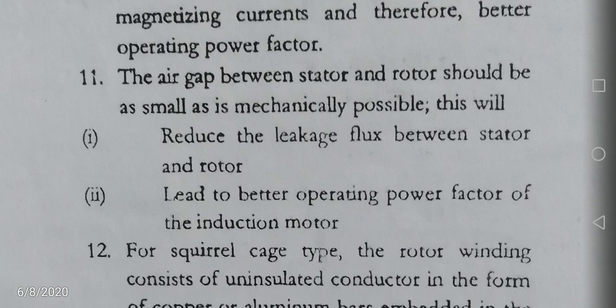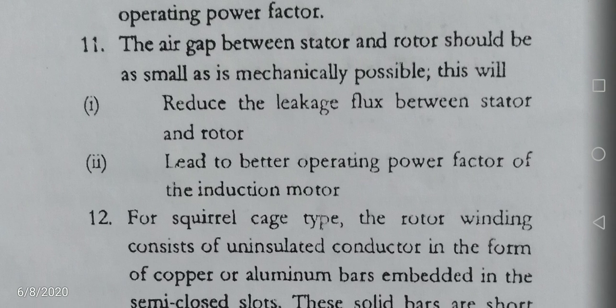It leads to better operating power factor. So if you reduce the air gap between stator and rotor, then the power factor of the induction machine is increased.